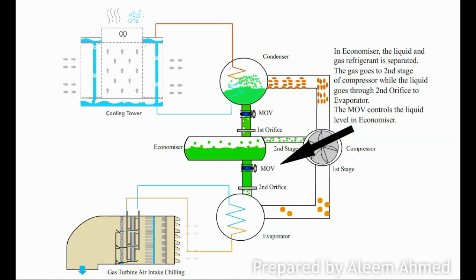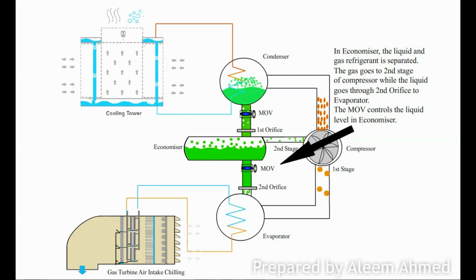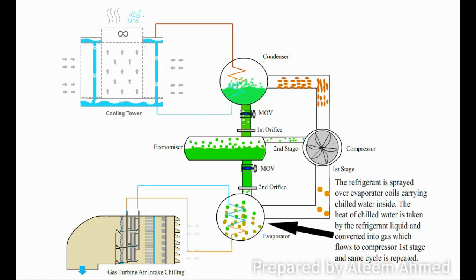In the economizer, the liquid and gas refrigerant is separated. The gas goes back to the compressor second stage inlet, while the liquid goes through the second orifice to the evaporator. The economizer MOV controls the liquid refrigerant level in the economizer.